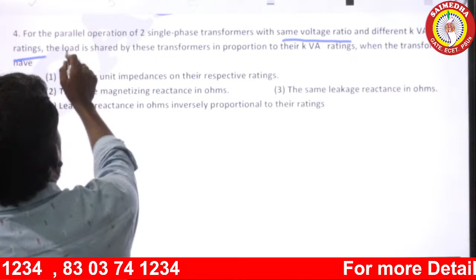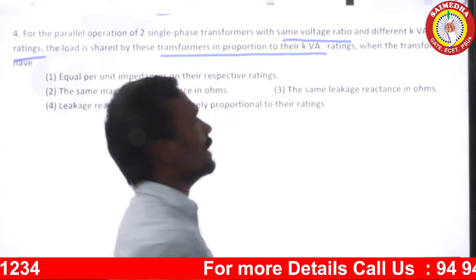Next question: for parallel operation of two single phase transformers with the same voltage ratio and different KVA ratings, when operating in parallel, the load is shared by these transformers proportional to their KVA rating.